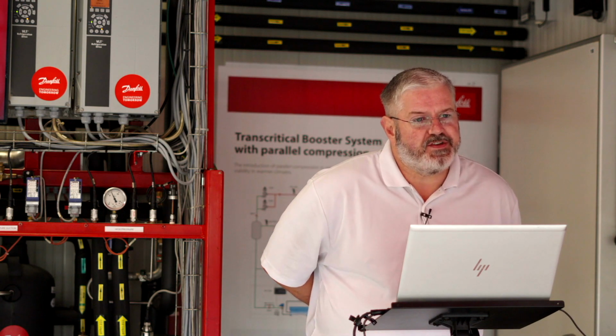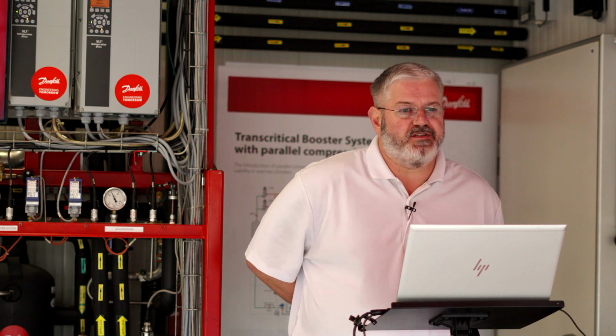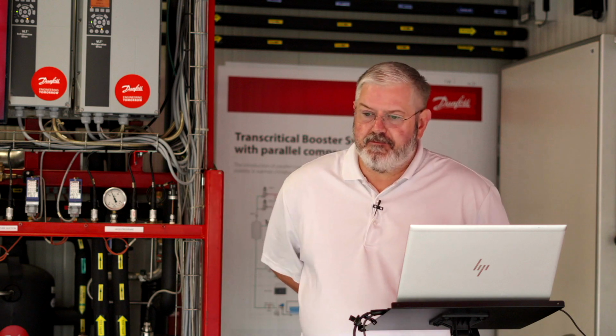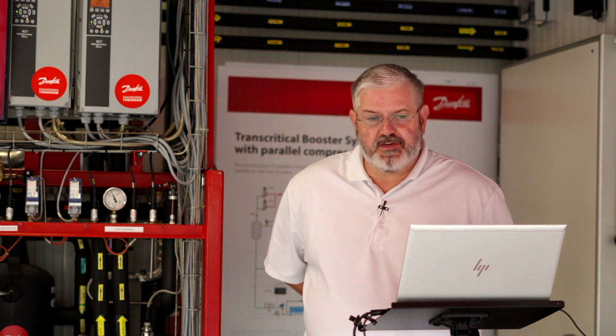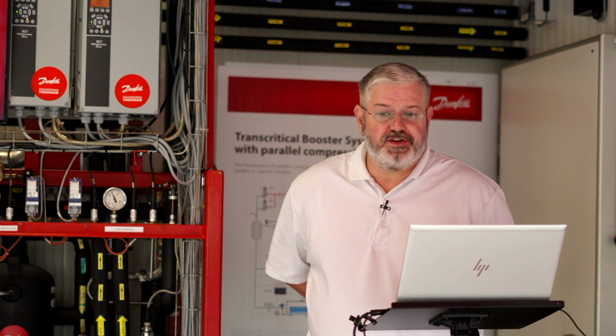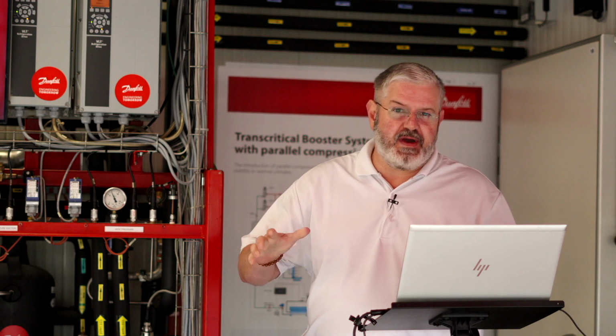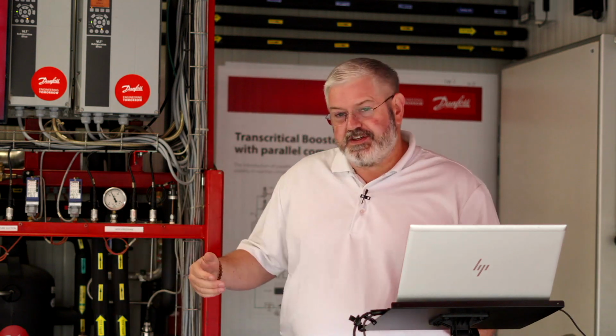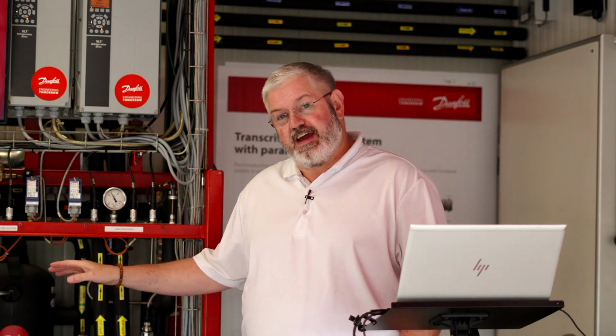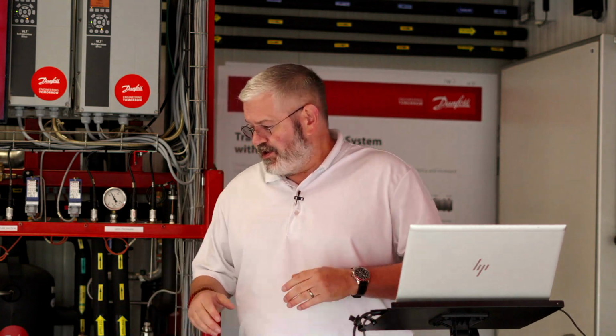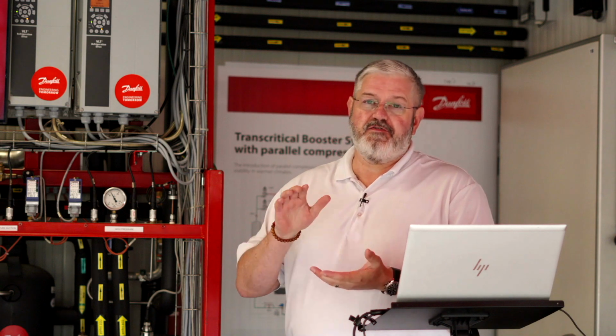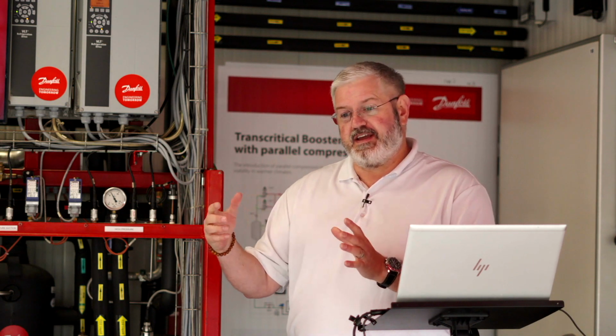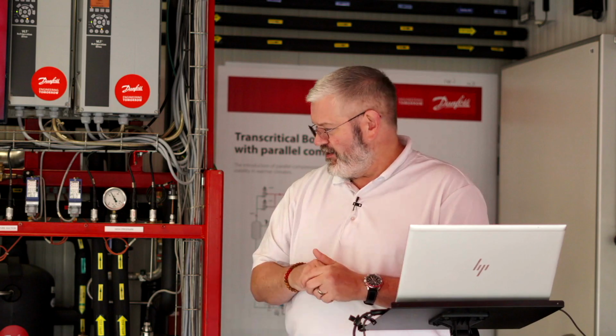And then we have another question: what's the best way to charge a CO₂ system? That's an excellent question. So charging the system, the first consideration is that CO₂ below roughly 60 pounds per square inch would be in a solid state. It forms dry ice. So if you pulled a vacuum on a system and you took a tank of liquid CO₂ and just started dumping, you're going to form dry ice inside the system. So you have two tanks for CO₂. You have a vapor tank, and then you have a liquid tank, and the liquid has a siphon tube down to the bottom of it.